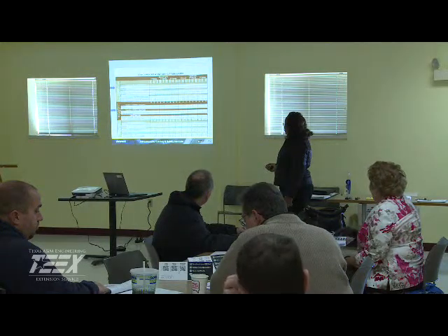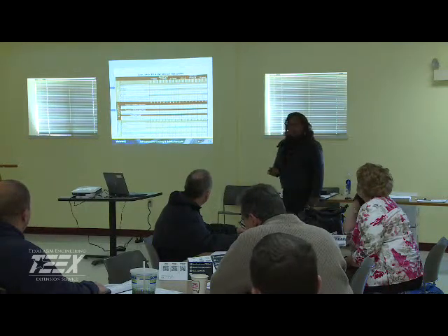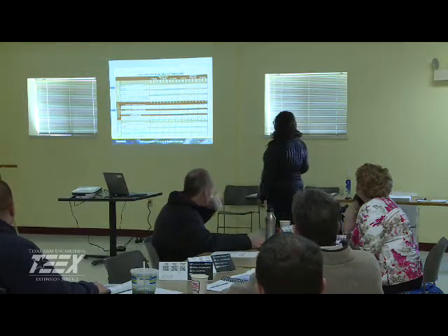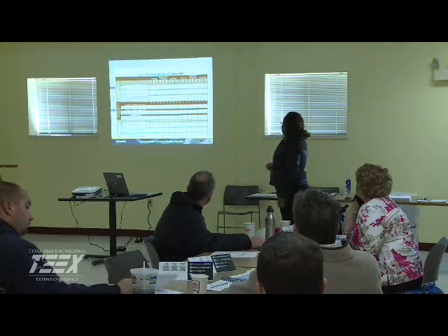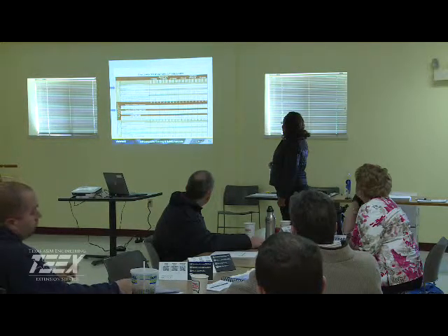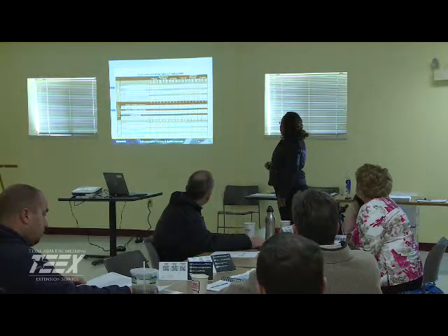Now, for the synthetic organics, again, with the waiver, look at that. No sampling requirements there. Otherwise, we're doing it, and this is for a population greater than the small system size, you're doing them twice. If you're a smaller system, below the 3,300, which is a small system, again, with the waiver, no sampling. Without the waiver, we're doing it once every 3 years for the synthetic organics.